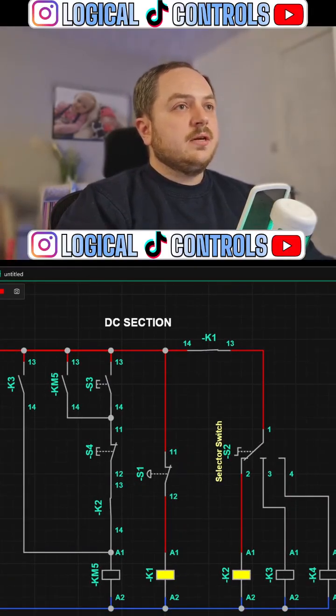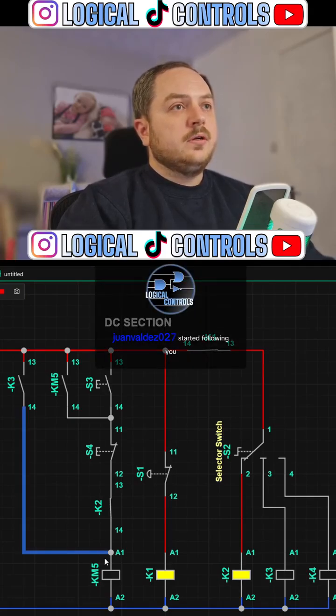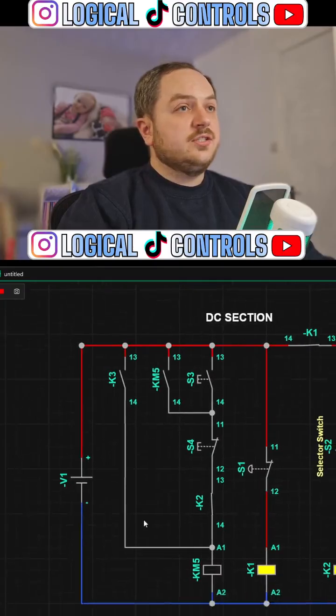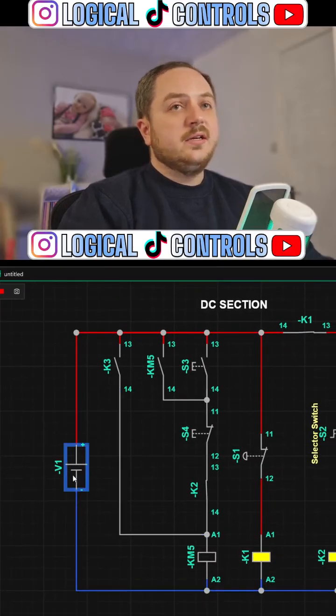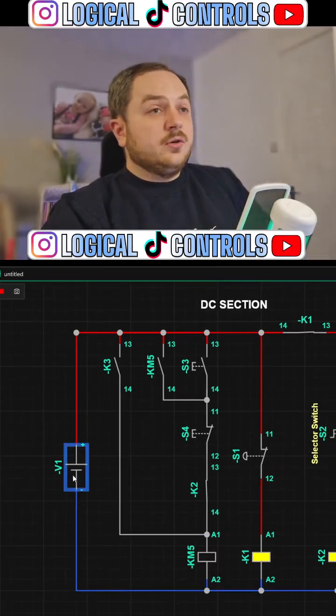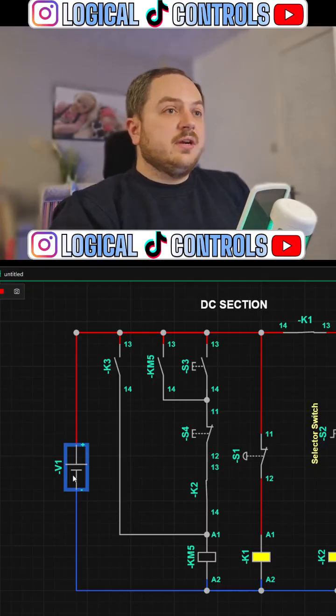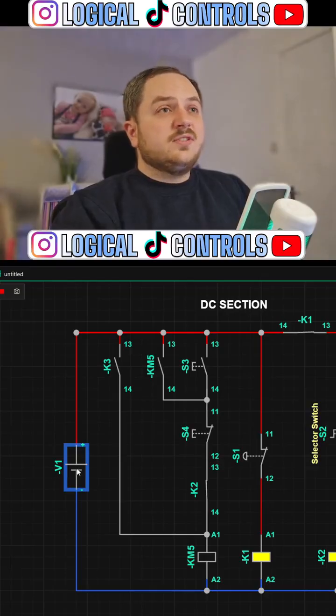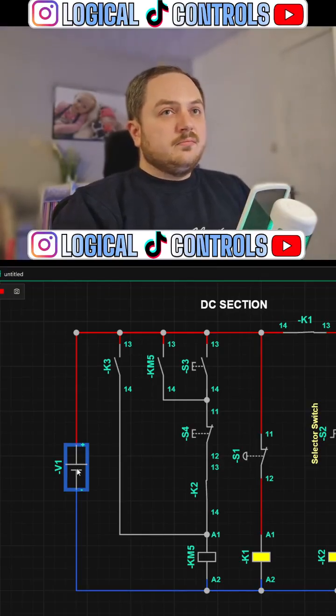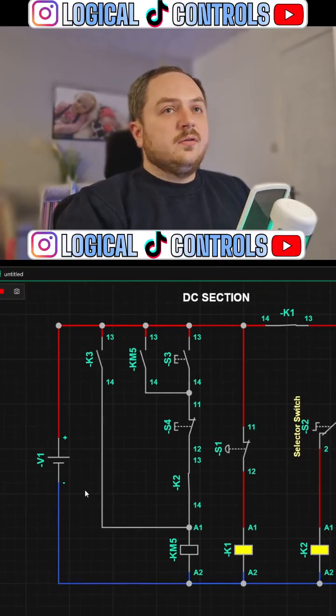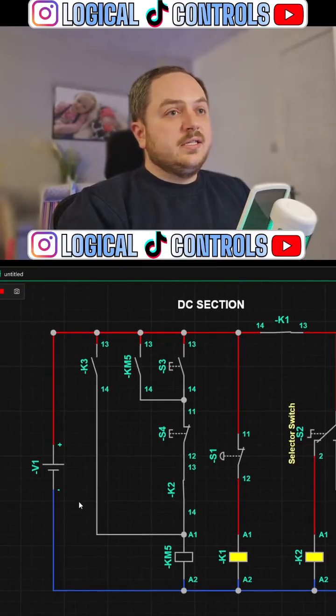Is there a step-down transformer for the controls, or is it powered separate? In this case, it's just 24 volt DC from a battery. In reality, you could have a battery. We use batteries a lot in generator control panels. We just put a small set of like MP1212 cells or something like that to keep certain controls up while the power supply goes off or whatever. But a lot of the time, it's just an AC to DC power supply.